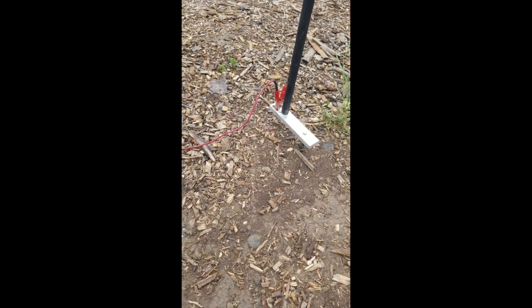One other thing, just for consistency, once I've marked the cable with my route tracer or cable locator, I proceed down the cable route. As I'm looking down the cable route from my transmitter, I stand on the right side of the cable for consistency with the red probe, like that, in my right hand, because that corresponds to the meter, with red on the right, black on the left. So my black probe's over here.